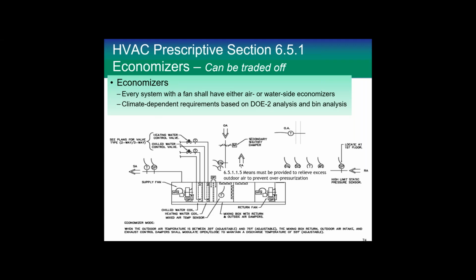Means must be provided to relieve excess air to prevent overpressurization. So you'll have to have some way to get that air out of there, so the building, you can shut the doors to the building and everything. Relief air outlet located to avoid recirculation. So this air that you let out of the building, we want to make sure you don't suck it right back in.